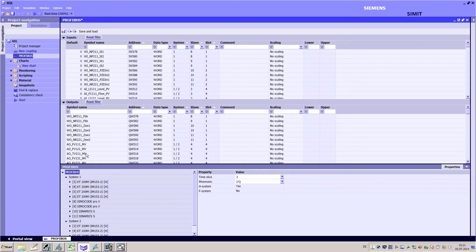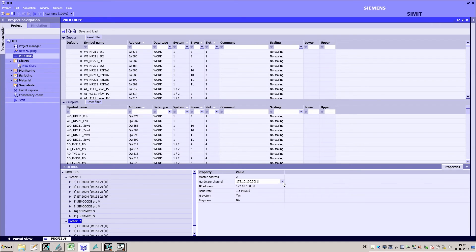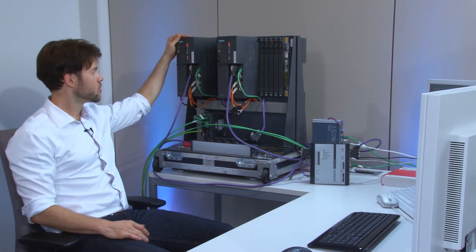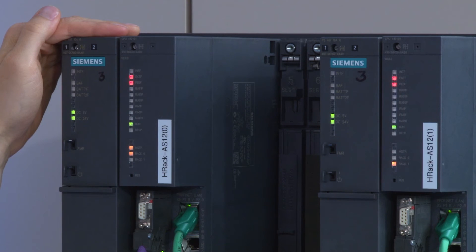After the import process I complete the configuration by allocating the relevant PROFIBUS channels to the simulation unit. In the example these are channels 0 and 1. Then I load the configuration into the simulation unit. When the red bus fault LEDs go out I can see that all the slaves have been recognized correctly.